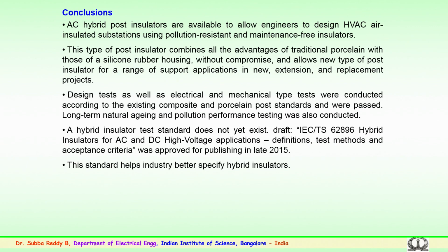And for long term natural aging and contamination performance, insulators are also being tested with the available standards. A hybrid insulator test standard presently does not exist. It is in the draft stage: the draft circulation, IEC TS 62896 on hybrid insulators for both AC and DC high voltage applications, which defines the definitions, test methods and acceptance criteria, is being approved for publishing soon. Once standardized, it will be adopted for the testing of hybrid insulators, that is, the post insulators used in substations and for equipment.